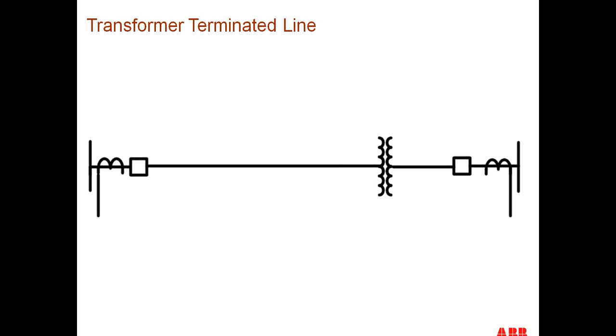Because we have a transformer terminated line, there are certain things we need to worry about, as we did with our transformer differential scheme. That is, when we energize this line and we close the breaker at the far end of the line to energize the bus and the line, we now need to worry about a transformer inrush current flowing into the transformer, which doesn't appear on our low side breaker at all, but appears on our high side breaker. We also need to worry about low side faults out here too, how to protect for those. So those are a couple things we're going to talk about right now.